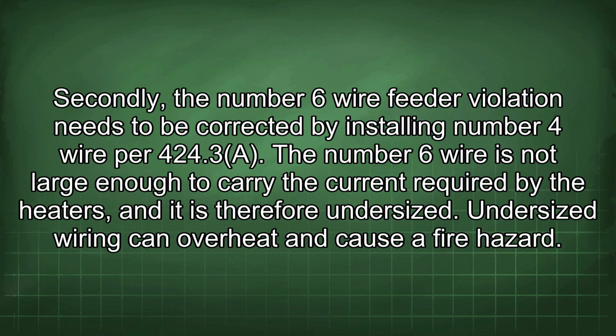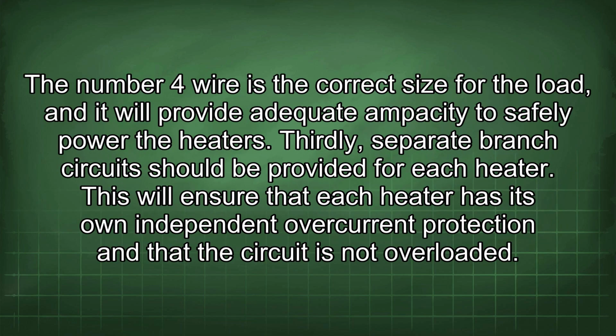Secondly, the number 6 wire feeder violation needs to be corrected by installing number 4 wire per 424.3A. The number 6 wire is not large enough to carry the current required by the heaters, and it is therefore undersized. Undersized wiring can overheat and cause a fire hazard. The number 4 wire is the correct size for the load, and it will provide adequate ampacity to safely power the heaters.